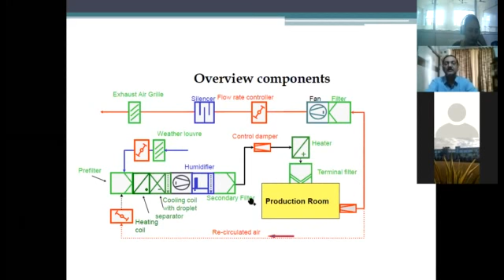When you are doing fumigation of the aseptic air in this production room, after fumigation all the air has to be removed. You cannot recirculate it, so you close this valve, open that valve, and everything goes out. After all the formaldehyde vapor has been removed, you close the exhaust and open the recirculation. That's how these systems are operated, and one has to be very careful that they are maintained properly. Otherwise, if the environment of the aseptic area is not correct, the product will be contaminated and become non-sterile. That's the importance of the AHU or HVAC system.